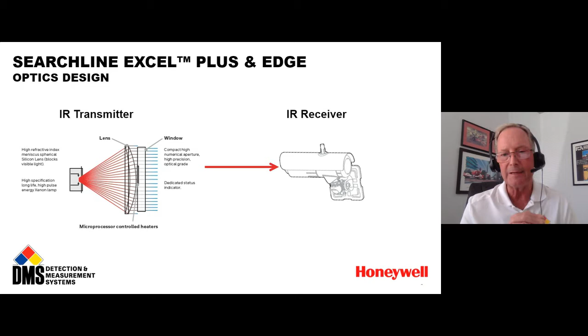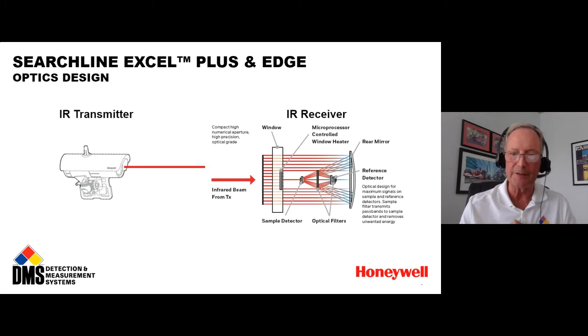And the reason for that is that they're bringing in more light, as you can see in the illustration. They're bringing in all of this light that enters through this large lens, where it hits a concave mirror, which focuses and folds that light and focuses it on a beam splitter that sends a portion of the light to a sample sensor and a portion of the light to the reference detector, but far more light than the previous Searchline Excel or anything else on the market. And that's the trick. We have a greatly improved IR source with a much more intense light beam that's better focused, going to a receiver that's taking in much more of that light and focusing all that light on those very small sensors. And that's what gives us these very, very long operating distances, which is, I think, absolutely brilliant. And so, if we look at this a little bit closer, let's look at this illustration here, which is a ray tracing of the light beam.